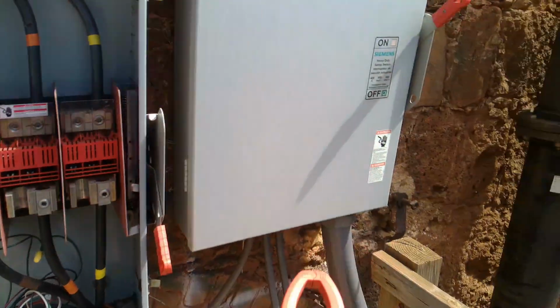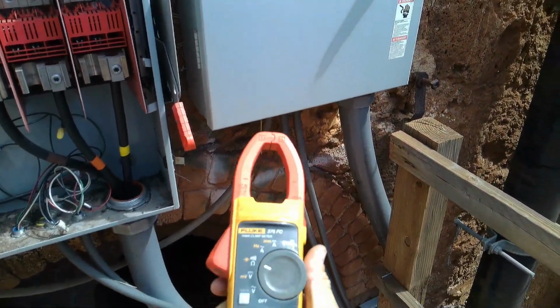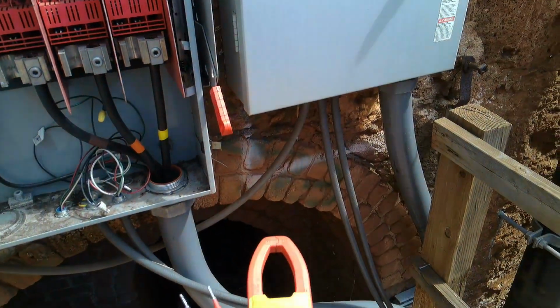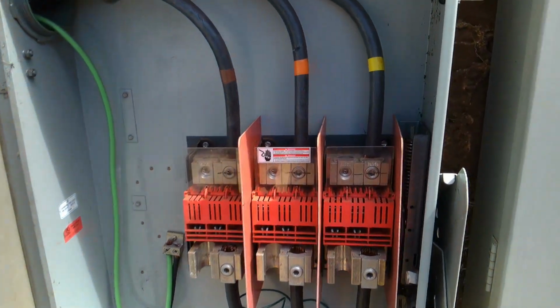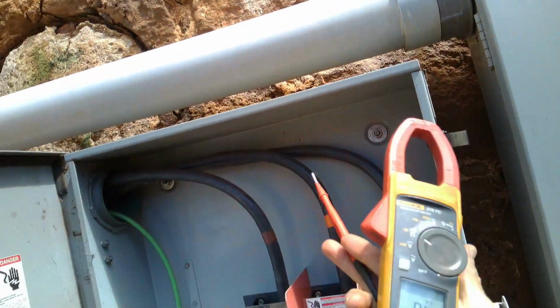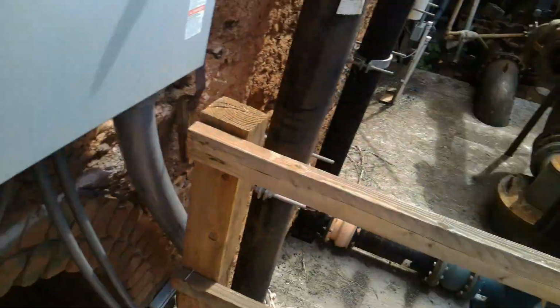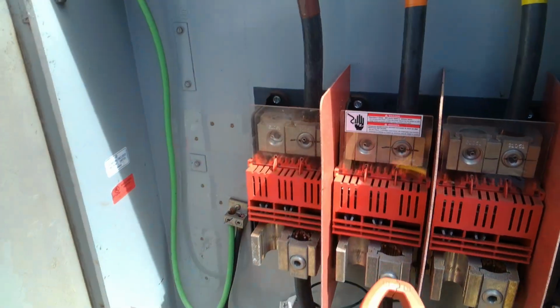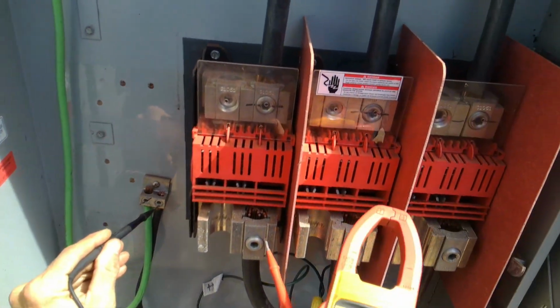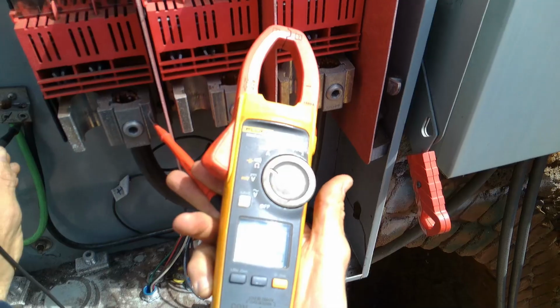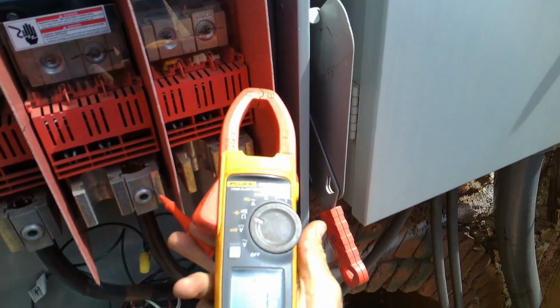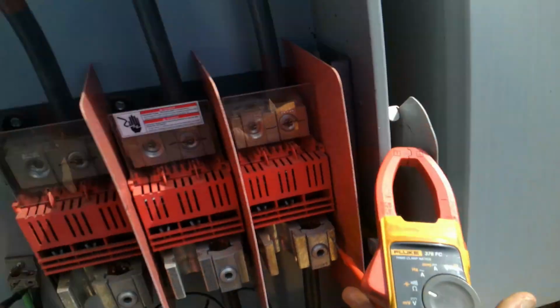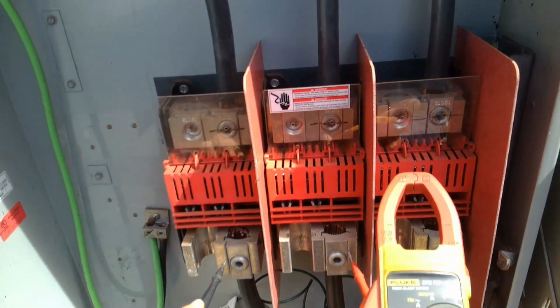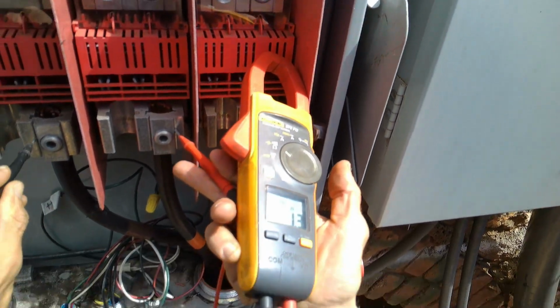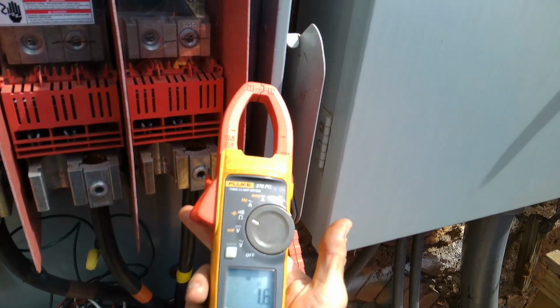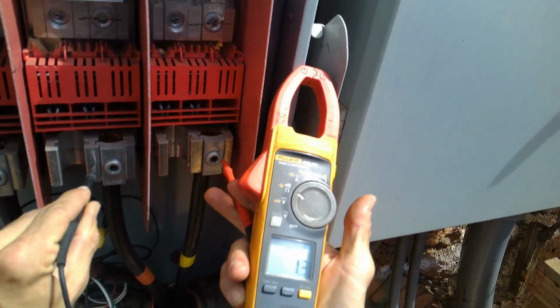Okay, so just to remove any doubt, because I don't want to just throw the words dead shorted motor around, I've got my 376 here just with ohms, and I've got my disconnect switch open. There's no power on the line side, but the switch is open. These are the motor leads. They go down right to motor 2's terminal box right there. So, and here's its equipment ground coming back from there. 1.8 ohms. 1.8 ohms. 1.8 ohms. That is a dead shorted motor. 1.3 line to line. 1.5. Yeah, it is smoked.